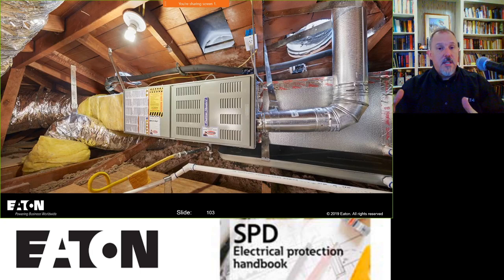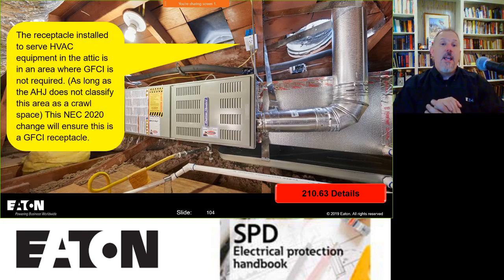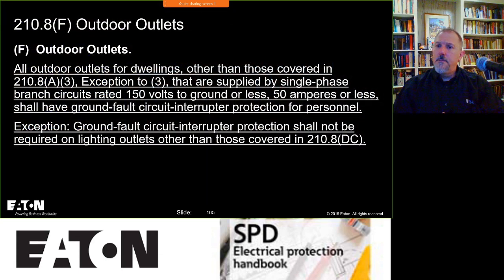This is another case where you have HVAC in the attic. Somebody could call this a crawl space issue, but if it's an attic with a taller roof and you don't consider it a crawl space, then that wouldn't need to be GFCI protected. But based on this recent change, that will have to be GFCI protected. There could be cases where you have equipment in any type of facility, not just a dwelling unit. This is around anything where you're putting a receptacle in for maintenance purposes, it needs GFCI protection. And test it before use, please.